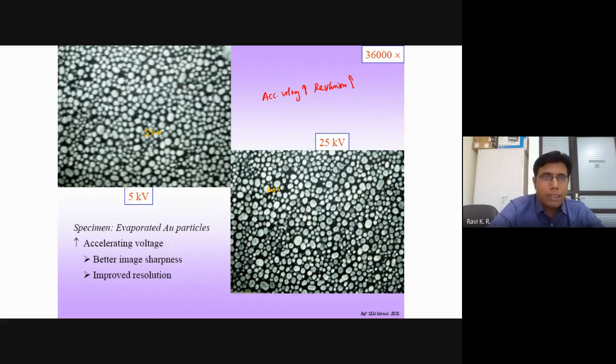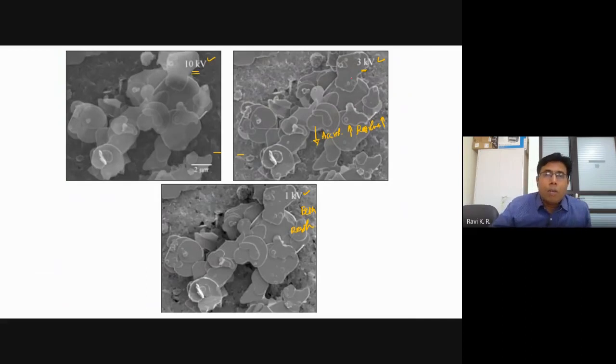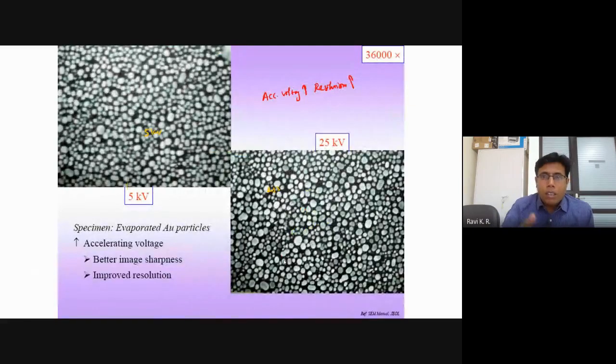That's fine. Astigmatism, we are correcting it. That is fine. You don't have much control. So coma, these we can actually control, but still you can see these two images. Please see here, it is giving the information that if you decrease the acceleration voltage, it is better. And here, if we increase the acceleration voltage, it is getting better. Then what could be the reason for that? We already discussed this point a little bit earlier, but now you have to connect it.